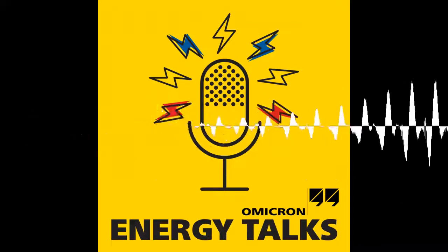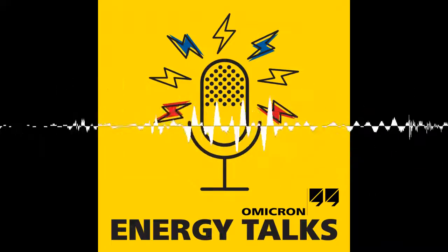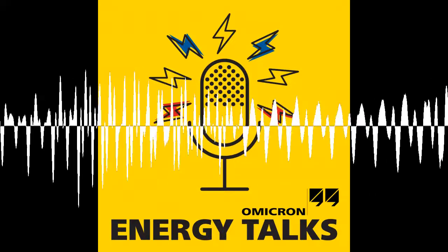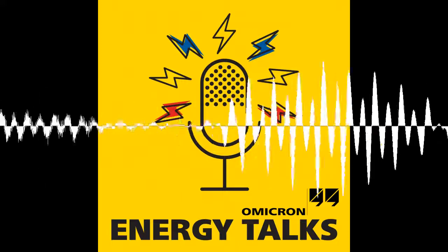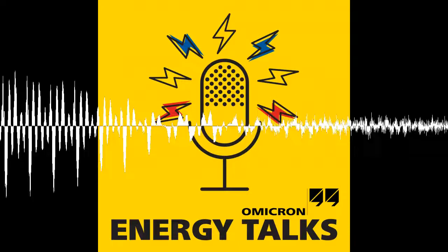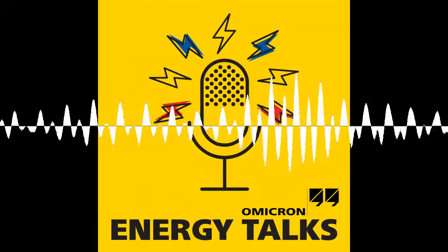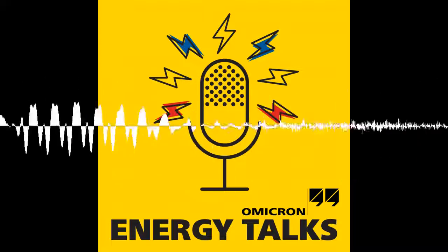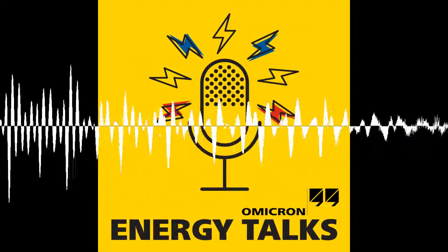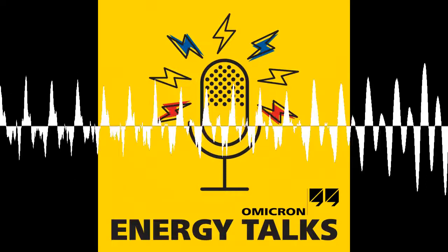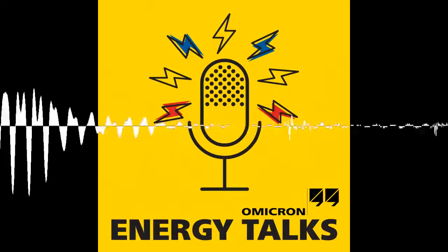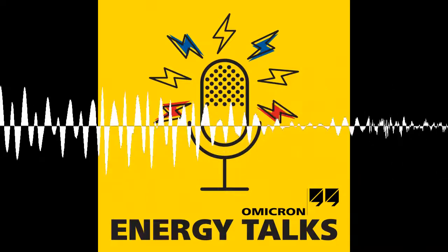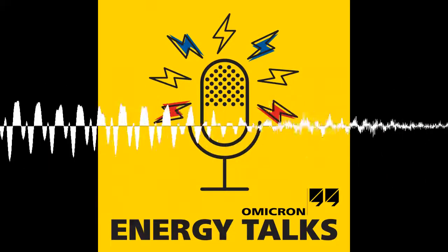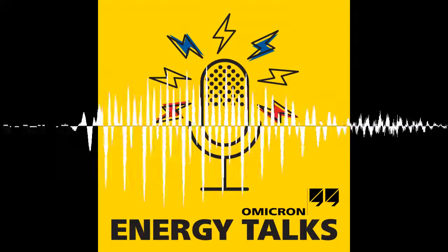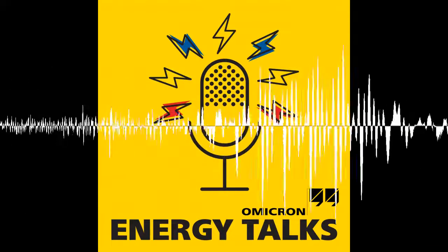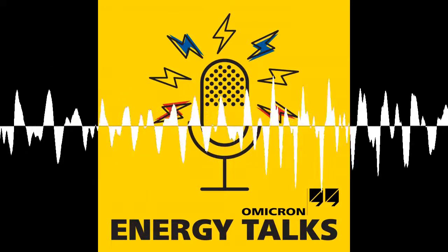And we recently launched also 2 new application videos. One about grounding system testing with the CPC 100 and one about testing grounding systems in medium voltage distribution substations, which contains also a lot of background information, and both can be found on our YouTube channel. Also, the Omicron Academy can perform grounding system trainings. Usually they do it on request by the customers and then can also customize the training to the customer's need.